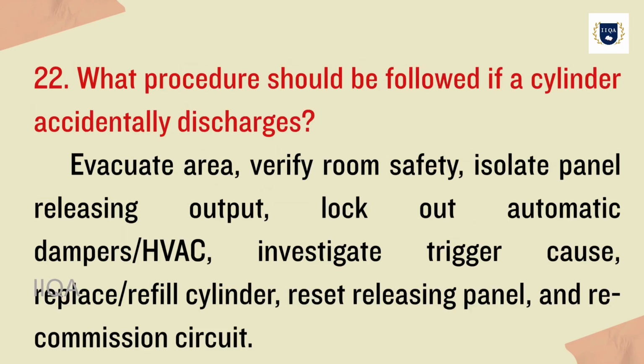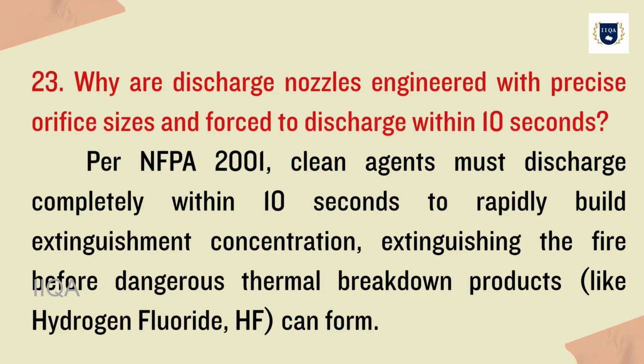22. What procedure should be followed if a cylinder accidentally discharges? Evacuate the area, verify room safety, isolate the panel releasing output, lock out automatic dampers and HVAC, investigate the trigger cause, replace or refill the cylinder, reset the releasing panel, and recommission the circuit.